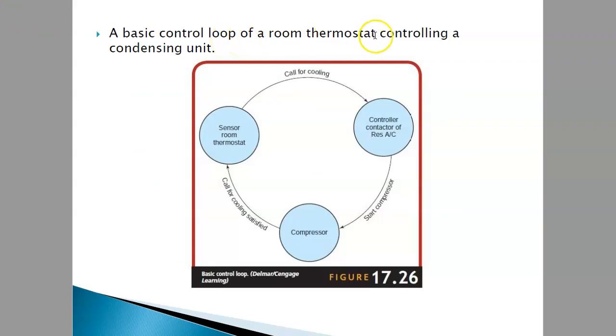This is a basic control loop of a room thermostat controlling a condensing unit. First we have the sensor, the room thermostat, which has to measure the temperature. When the temperature is high, it will send a call for cooling to the controller that controls the aircon system, or the microprocessor. It sends a signal to start the compressor, and the compressor moves. When the sensor senses the temperature has reached 24 degrees, if we set 24, it will send a signal that this one should be off, or the inverter is slowed down to maintain the temperature at 24 degrees.